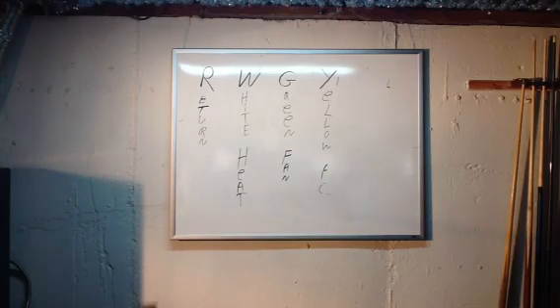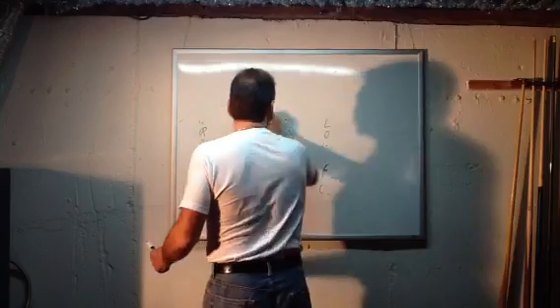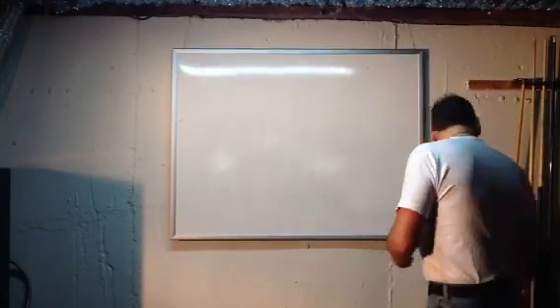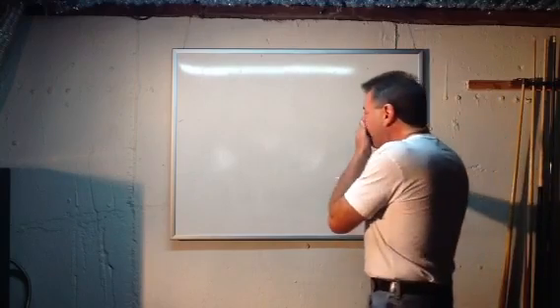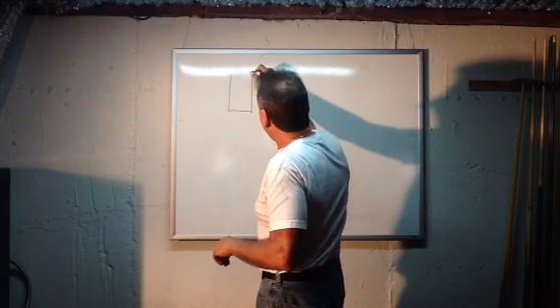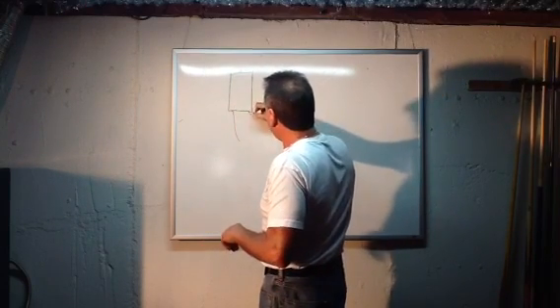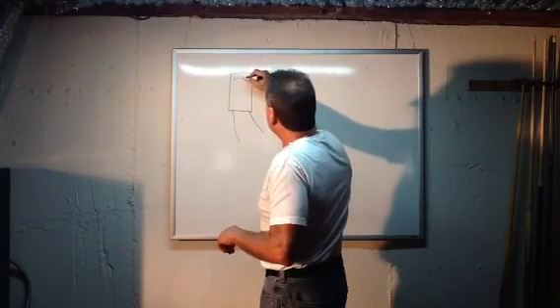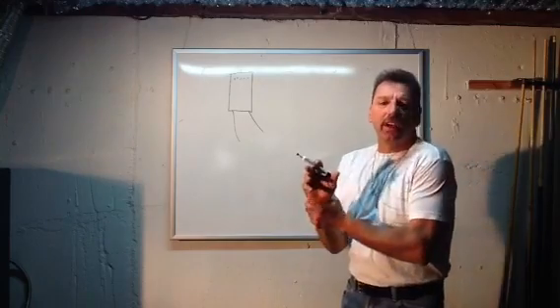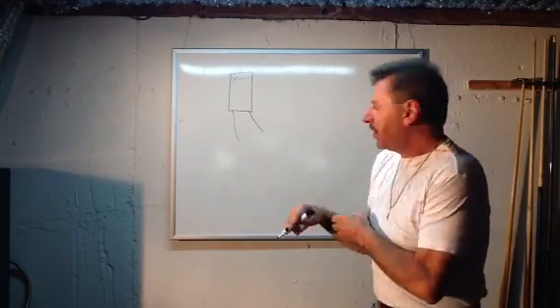Another quick way of wiring a zone on a boiler—now this is different. We were talking about a 24-volt thermostat there; now this is a line voltage thermostat. Line voltage thermostats are a little different and not really as accurate, but basically they have two wires sticking off of them. To add a zone to a boiler, instead of going crazy with all the relays and controls, it's very simple.